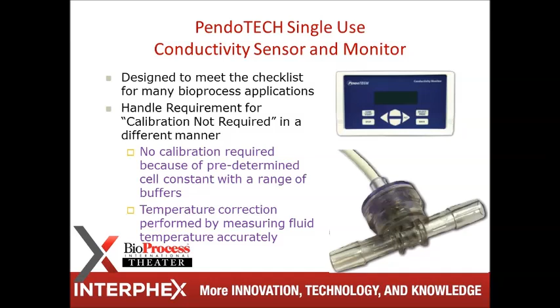This is an example of our conductivity sensor. So there's no calibration required because we predetermined the cell constant. So if that's a method that would be acceptable, we predetermine the K factor, and that's entered into the monitor by the user. So that's why a calibration is not required. And within the conductivity sensor is also a thermistor, which is very similar to an RTD, but with a more narrow range, but it's very low cost. It has the ability to very accurately measure temperature because of a defined resistance versus temperature. And that has a similar monitor.